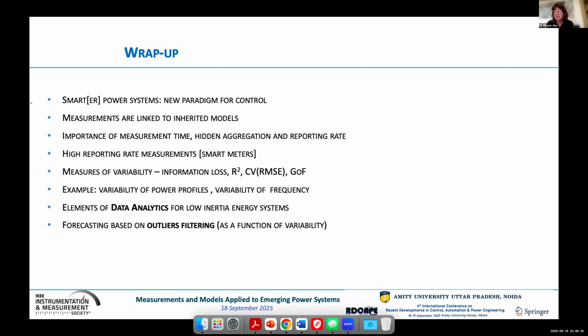The sampling rate has a big role when we think about the maximal error and uncertainty associated with the measurement equipment. The PMUs now, the most modern algorithms used by phasor measurement units, which are still the best measurement device for frequency, have a sampling rate of about 50 kilohertz, at least for those models in CompactRIO from National Instruments, so beyond 10 kilohertz. But that sampling rate only influences the error of the data given by the phasor measurement unit. From that point, suppose we reach below 0.1% total vector error and also very good low frequency error.